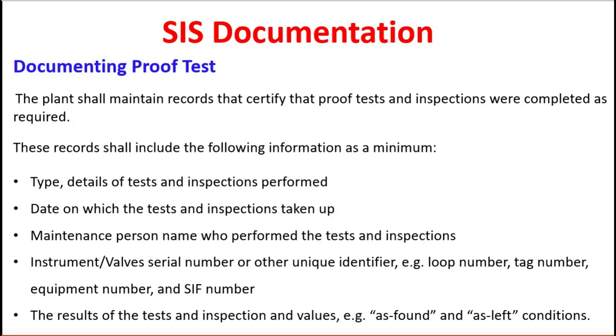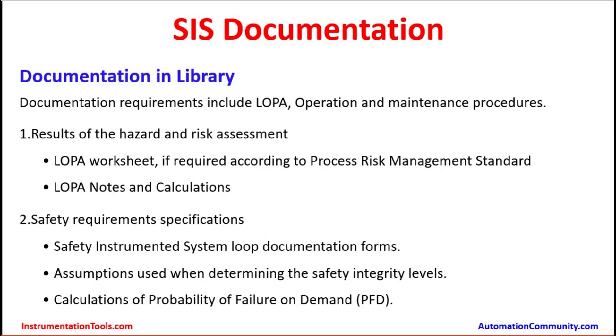Records shall also include the results of tests and inspections, including as-found and as-left condition values. During the initial point of the test, results could differ — for example, a 0 to 10 kg/cm² transmitter sensor could read 9.8 or 9.6. It will be 99% accurate, but there could be a small drift inside the sensor body. When it is calibrated and tested, accuracy has to be as close as possible to actual. Some documentation needs to be kept in the library for the plant's lifetime to support maintenance.